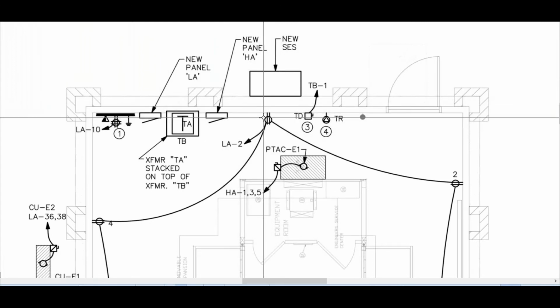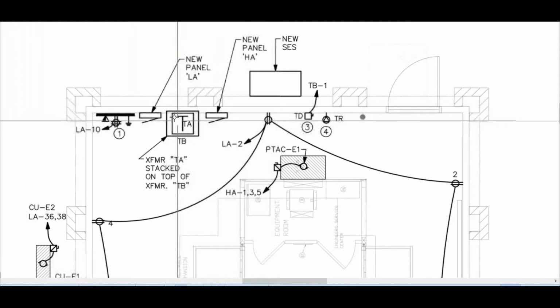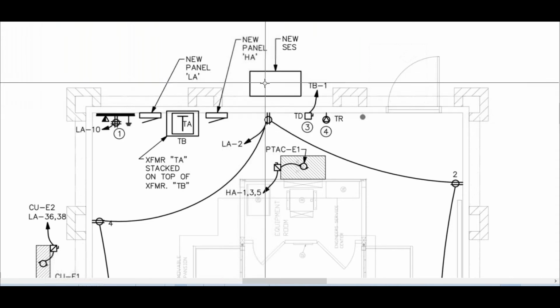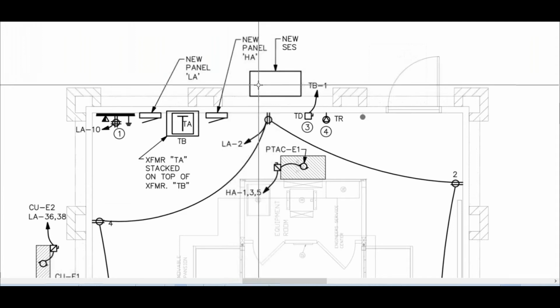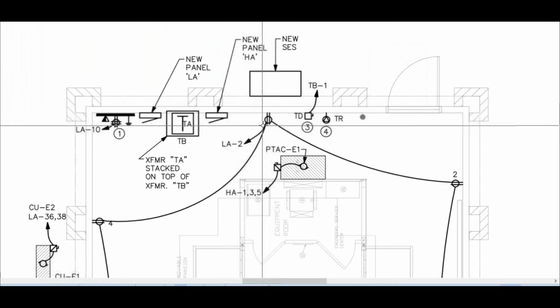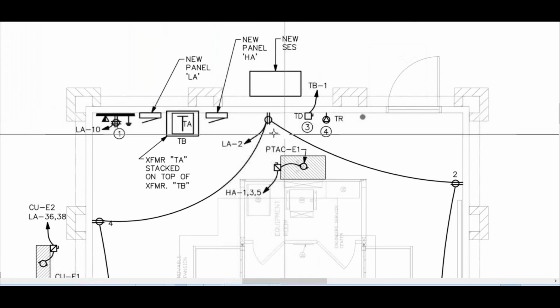There's another thing that's unseen here. You can't just stick a 90 of conduit going out through this wall. You have to transition it. This is a great example of using transitional material, from outside to inside. In this instance, I would use either 2 LBs—these are parallel feeders, 3-inch—or a big junction box on the wall up high, probably out of sight.